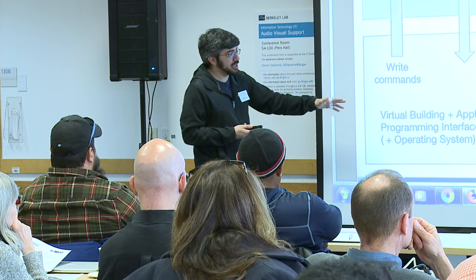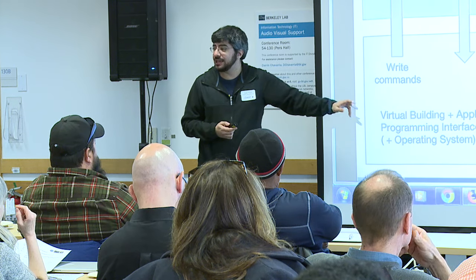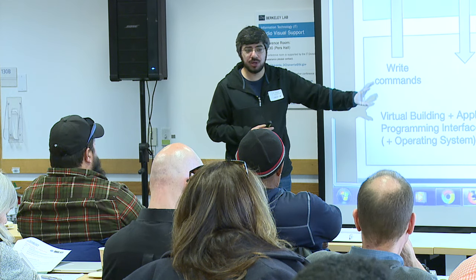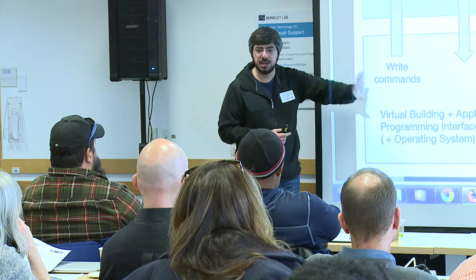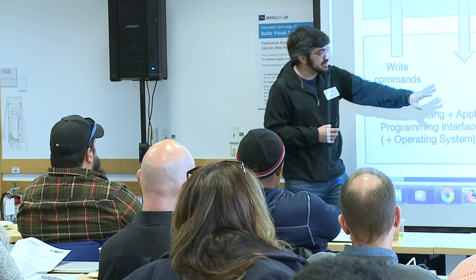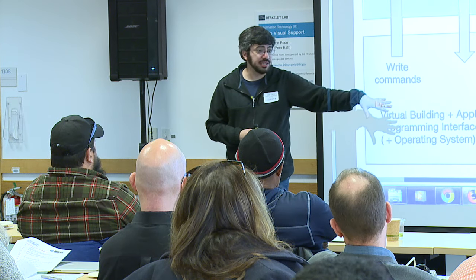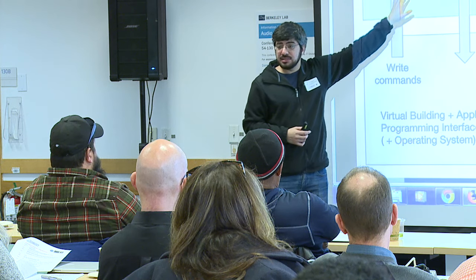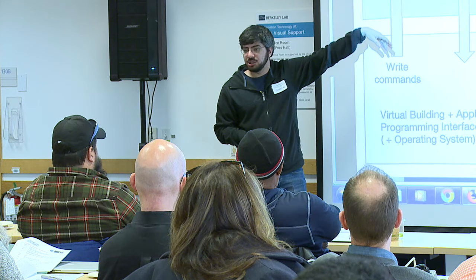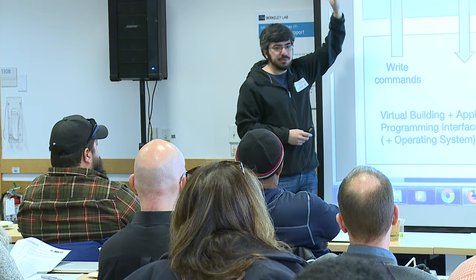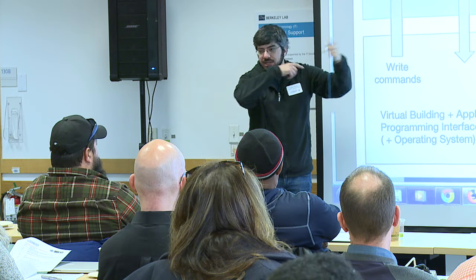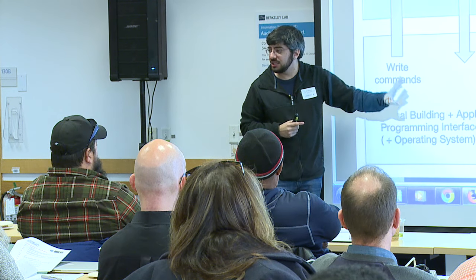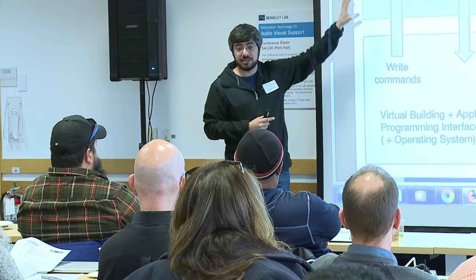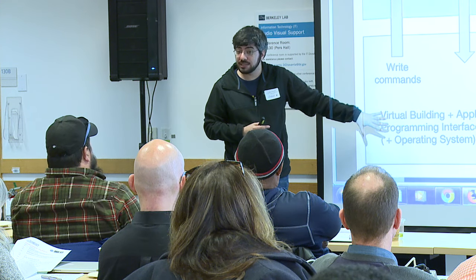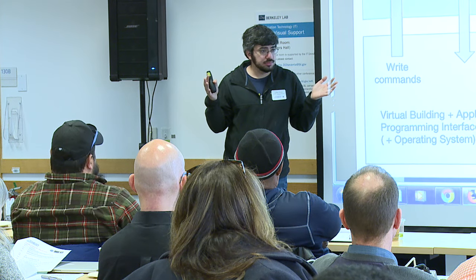Going from the digital twin, I can work with this using whatever tools I want—Excel, Java, Python, or some web app someone wrote, some open source software. If I standardize this, if I design the digital twin well along with that application programming interface, then I don't have to care what's underneath. It can be Siemens, KNX, BACnet over LAN, over serial, or even carrier pigeons carrying HVAC commands back and forth. As long as I have a sufficiently descriptive digital description, that doesn't matter. It means I can write code once and ideally run it anywhere, on any building.